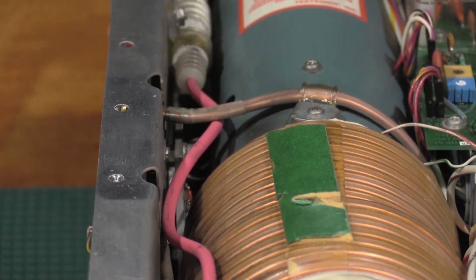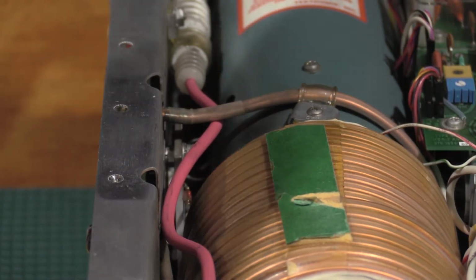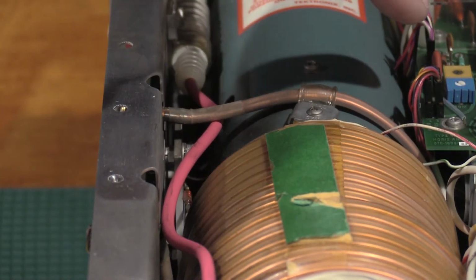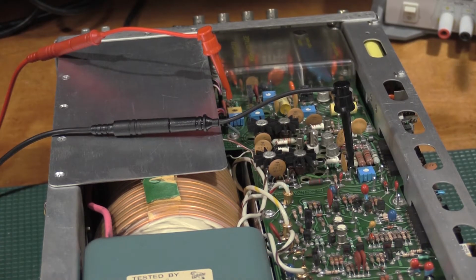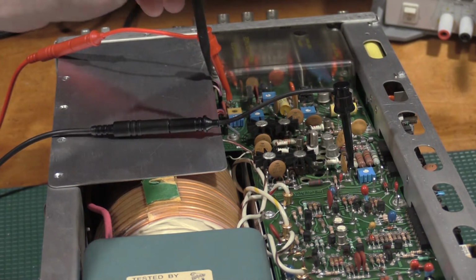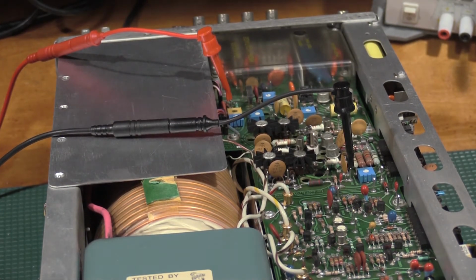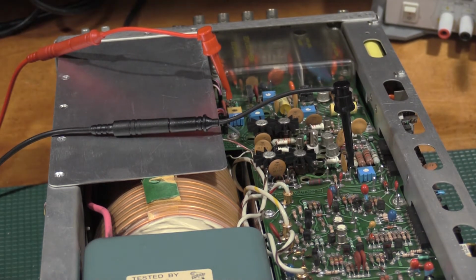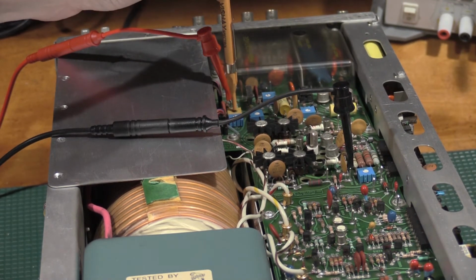I need to hook the meter up to... I'm going to put the shield back on, and then I've got to hook the meter up over here. Okay, so 1796, the PL comp resistor is right here. And my calculated average was 46.25. I'm reading 46.50. And I'm allowed 300 millivolts difference. So it's very close. I'm going to adjust it a little bit, see if I can't true that up just a bit. However, it is actually within spec.